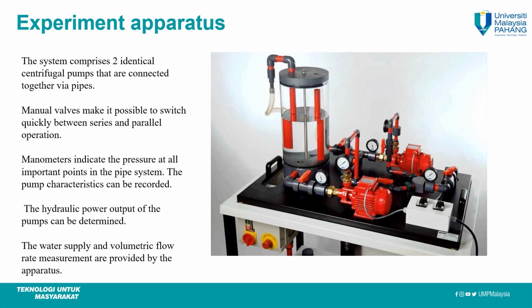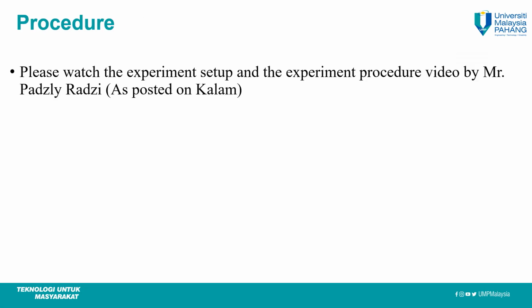The outpouring of the water creates a negative pressure, a vacuum, at the intake branch, and the water flows through the connected intake pipe. Depending on the pressure difference to be overcome, a single-stage or a multi-stage centrifugal pump is used. Centrifugal pumps generate a uniform volumetric flow without pressure surges, and consequently are the most common type of pump used for conveying fluids. There are different types of valves, reservoirs, centrifugal pumps, and flow meters connected. These are used for the simulation of pumps in series and parallel.